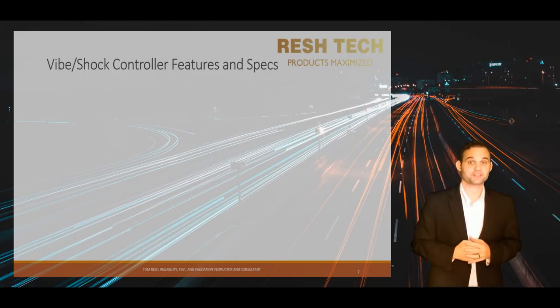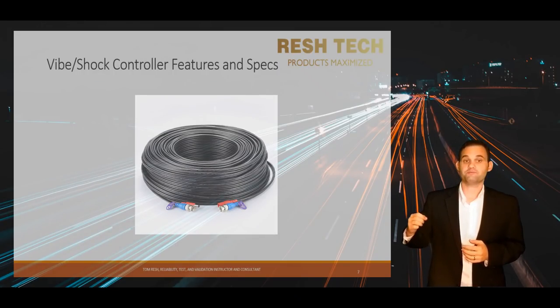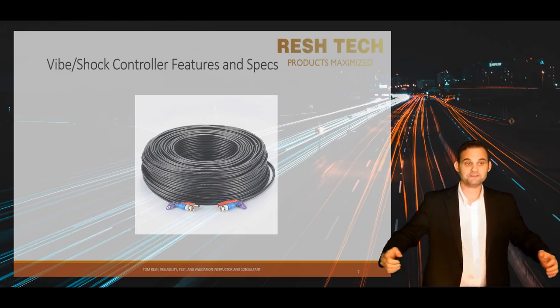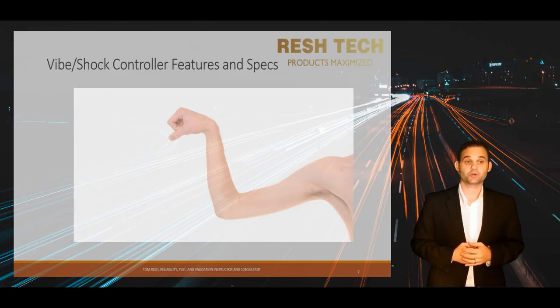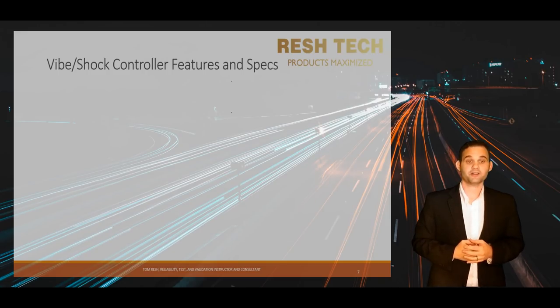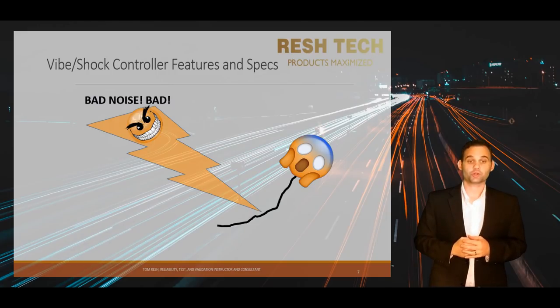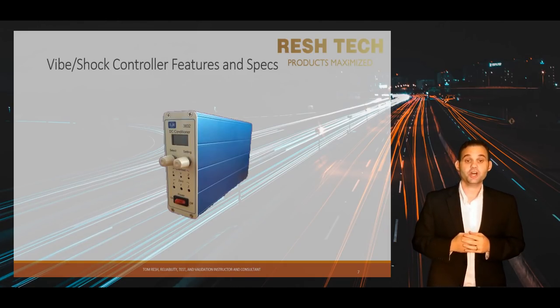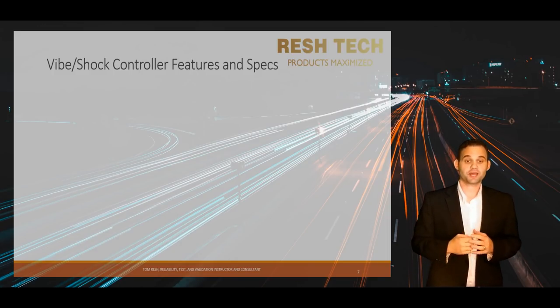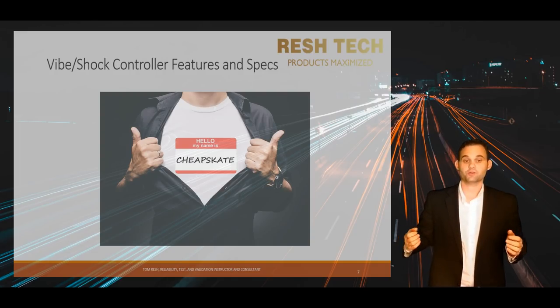Here's a tip you will not learn anywhere else, especially in a manufacturer's training course. If you are running a long run of BNC or accelerometer cable — more than 50 feet — the ICP power supply built into most vibe and shock controllers is insufficient for long-distance cable runs. You will pick up a tremendous amount of noise and can get a vibe controller abort message. If you are using a voltage mode accelerometer, you will need to purchase a separate power supply signal conditioner to overcome the voltage drop and clean up the signal. Also make sure you are using high-quality, well-shielded BNC cables for runs of 50-plus feet.